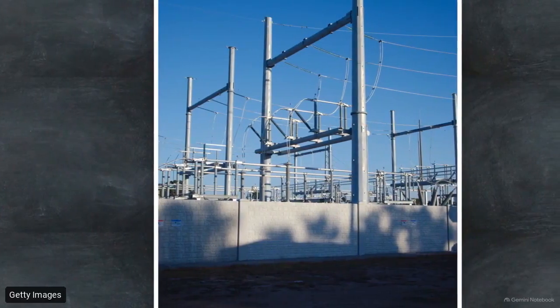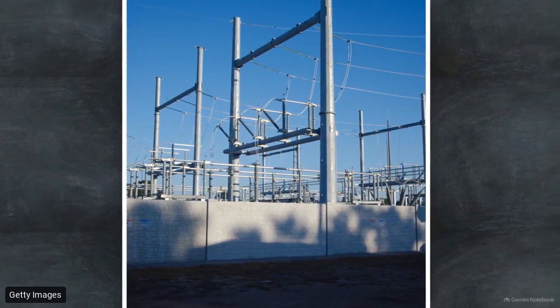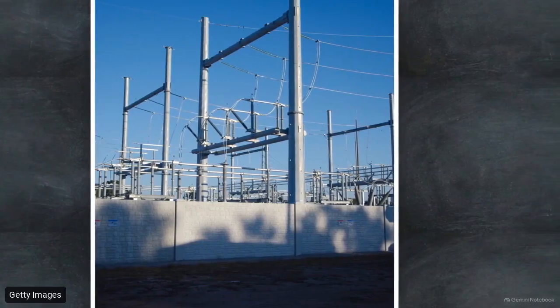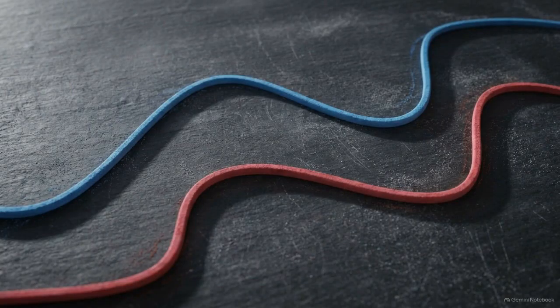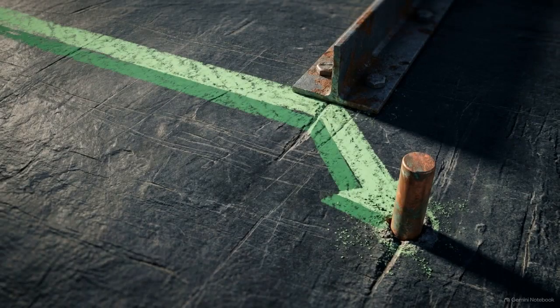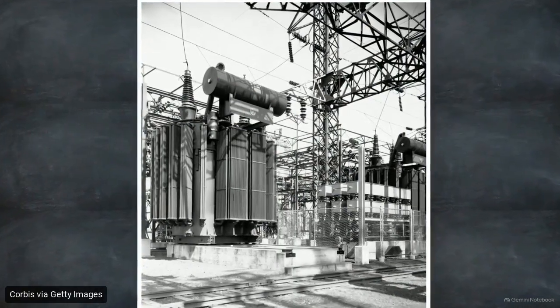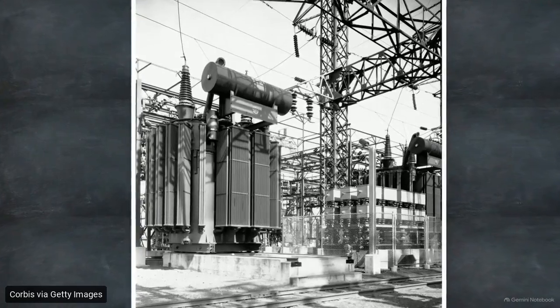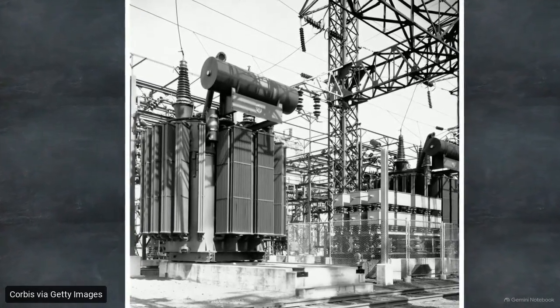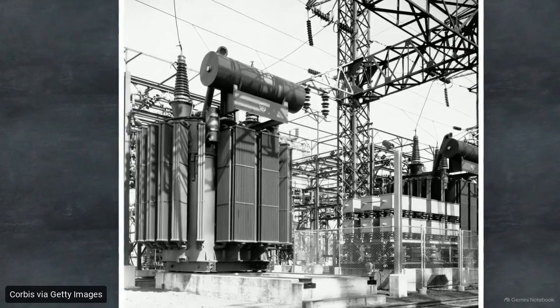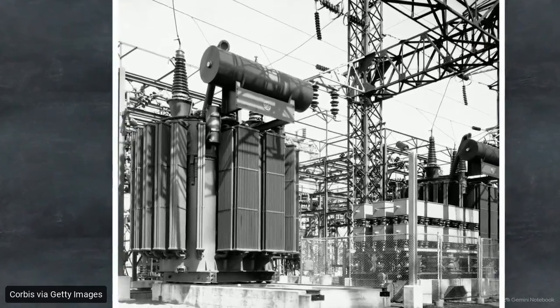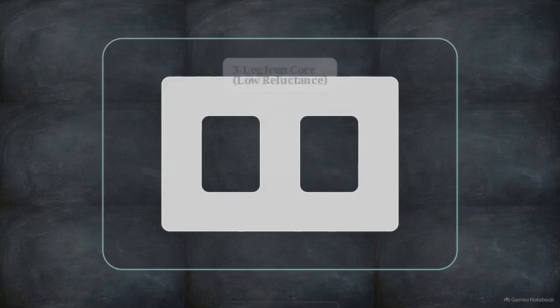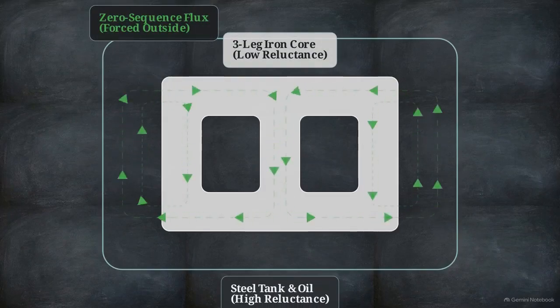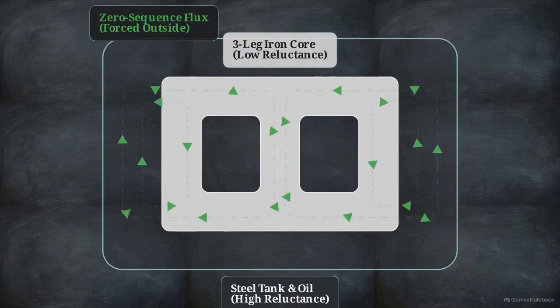These mathematically decoupled sequence networks must then map directly onto the physical topology of the actual grid equipment. While positive and negative sequences flow smoothly through the system, the zero sequence network is strictly constrained by physical grounding paths and the internal geometry of transformers. Take the structural design of these large-scale step-down transformers. We classify them by their magnetic cores, distinguishing a shell-type transformer from a three-leg core-type transformer. In a three-leg core-type transformer, the zero-sequence flux generated by the three phases has no low-reluctance iron path to return through.